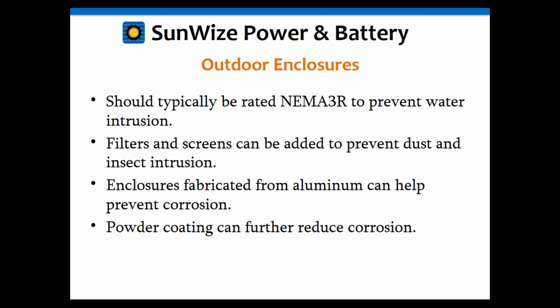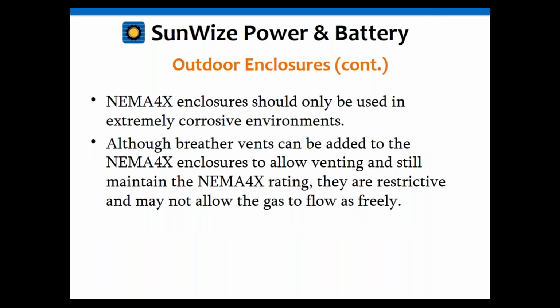Enclosures fabricated from aluminum can really help with corrosion, and powder coating it can help even further. A powder coated aluminum enclosure can actually be considered NEMA 3RX and corrosion resistant. Aluminum enclosures are also easier to work with since they're lighter than steel, and you don't have to worry about rust. There are a lot of advantages to aluminum over steel—lighter weight for shipping and installation, plus corrosion resistance.